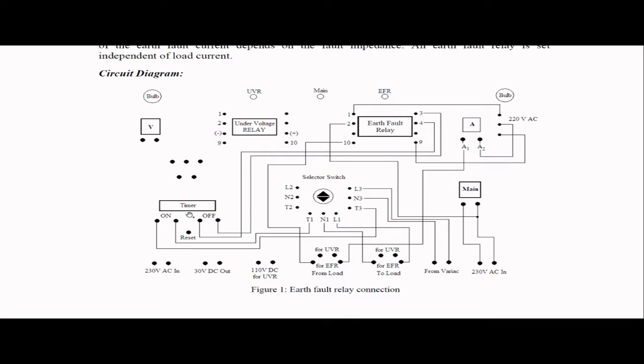Now this is one digital timer. This digital timer has four terminals, two for the on and two for the off. If I give a short circuit pulse on the on terminals, then the timer will start counting. And if I give a short circuit pulse on the off terminals, then the timer will stop. Here you see these on terminals are connected to T1 and T3. That means if I put the switch in the downward position, then there will be a short circuit pulse on the on terminals of the timer, so the timer starts counting. These off terminals are connected to the 3 and 4 of the earth fault relay, which are nothing but the trip signals. When the relay senses a fault and generates the trip signal, then 3 and 4 will be short circuited, and this short circuit pulse is connected to the off terminals of the timer, and the timer will stop counting. So this timer indicates the relay operating time.